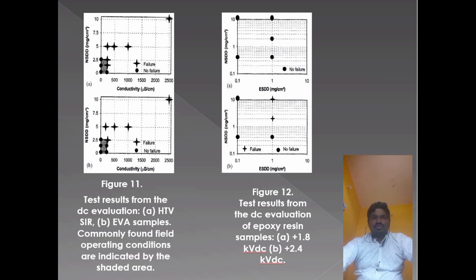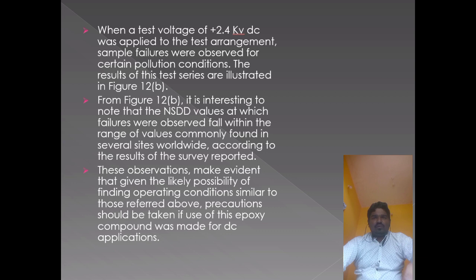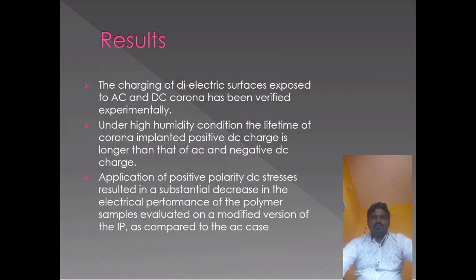A more critical situation was experienced when the higher test voltage of 2.4 kV DC was applied to the test specimens. When a test voltage of 2.4 kV DC was applied to the test arrangement, sample failures were observed at certain pollution conditions. The results of this test series show that the failures observed fall within the range of values commonly found at several sites worldwide. This may not be considered as levels commonly found in the field, except for those locations near the sea coast. However, precautions should be taken if the epoxy compound is used for DC application. The next part will be the results.